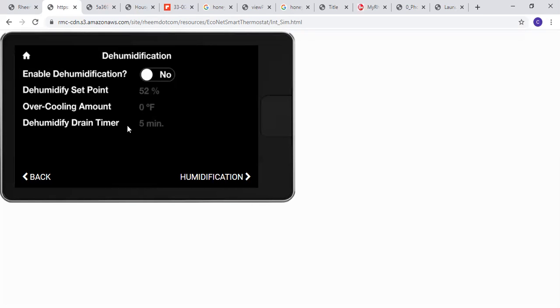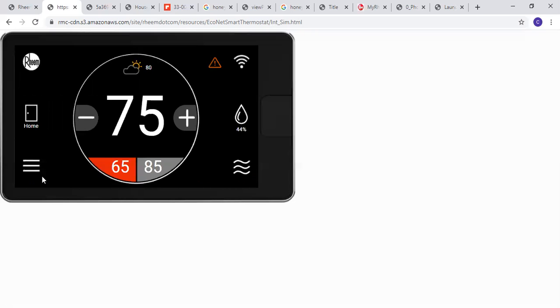So if your fan's running all the time, you can take some of that moisture and put it right back into the airstream again. So this dehumidify drain timer is set for 5 minutes for the fan to shut off and give it 5 minutes for that moisture to drain. You can turn it off if you want to, but if you were to get a complaint that after every air conditioning cycle, my fan turns off, then it magically turns back on in a few minutes, that's the problem.